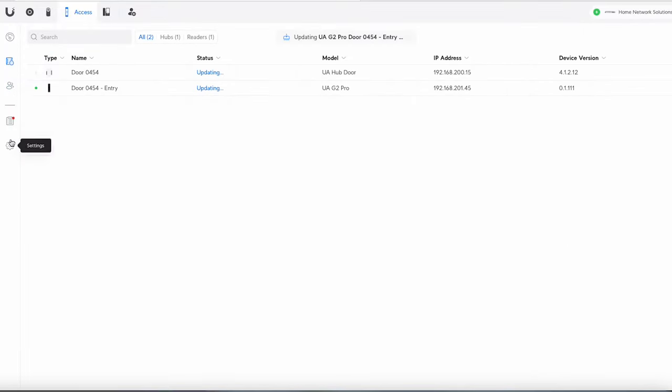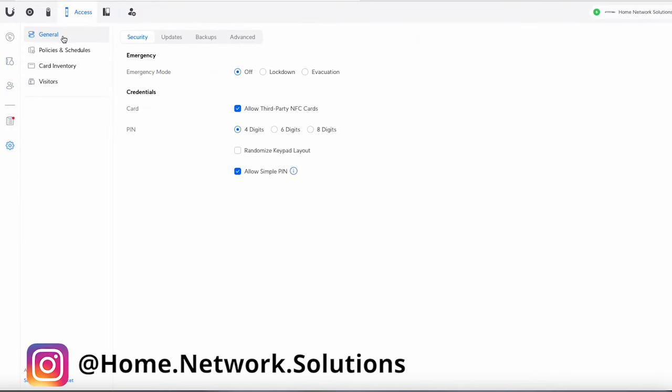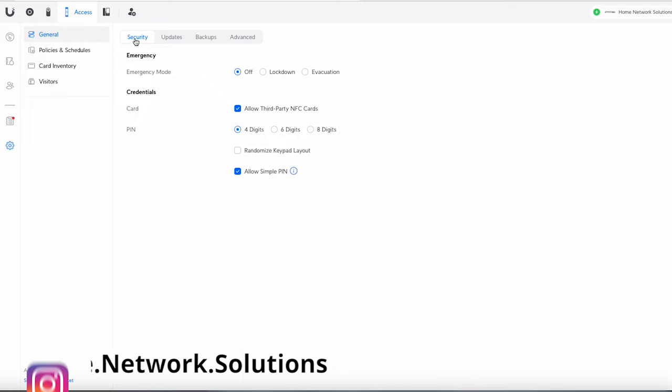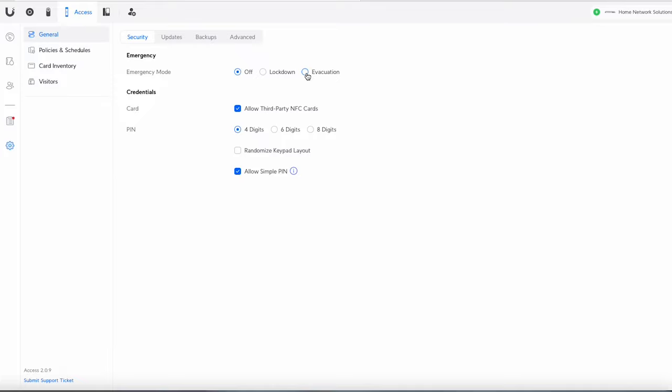Okay so we're still updating so we'll go down to settings and take a look at some of this. So we look in general we've got security policies first of all. So basically emergency mode means what's going to happen when your emergency systems kick in. So this will be fire. Now I've not linked the fire system or a fire system to this but if you did have a fire system you can put it into the hub and essentially you're telling it what it's going to do in that situation. So ideally you want everyone out. So you're going to click evacuation and basically that's going to unlock all the doors so everyone can get out. They're not going to get held in by the mag locks. So that's what that bit is for there.